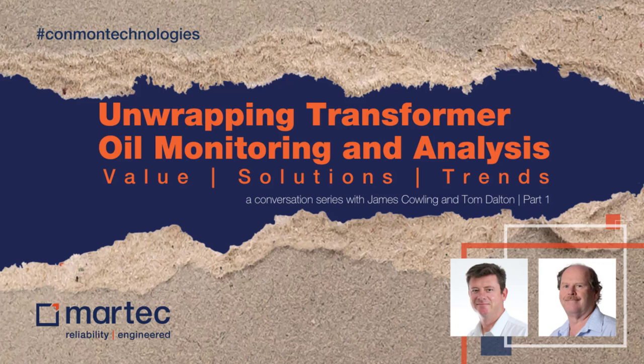We then also supply permanent online monitors from composite gas, which are effectively single gas monitors, all the way through to 11 gas monitors. Those are the ones that sit in the level 3 diagnostics, where we're looking at the different types of gases. We can determine whether we've got partial discharge. We can determine whether we've got arcing in the transformer. We can determine whether there's a core fault or the paper is being affected by heat. So there's a lot of the analytical side that we can do on that side.